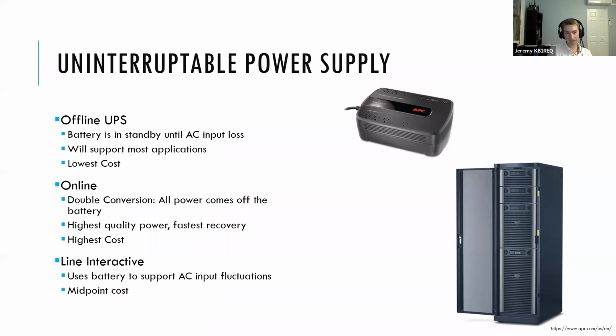Your online power supply, as the name implies, and contrasted with the offline power supply, performs what's called double conversion, meaning all of the output power coming from that UPS is actually coming off of the battery and is converted to AC. So your input comes in, is used only to charge the battery, and then your entire load is running off that battery all the time. So it gives you very high power quality and a zero recovery time from input power loss, because you're always on the battery, you're always pulling off those batteries. Your devices never see power loss. They never see mains power. And highest cost with these, obviously.